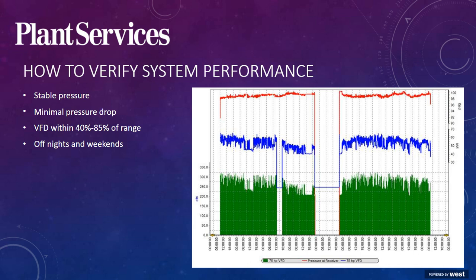And if you see here, you've got some periods that are white in the middle, and so they've actually turned the system off most likely on the weekend or overnight one day. So, there's some found money there as well.